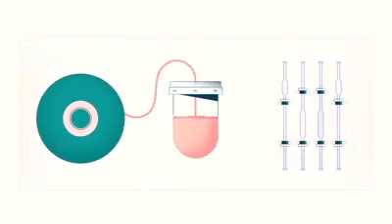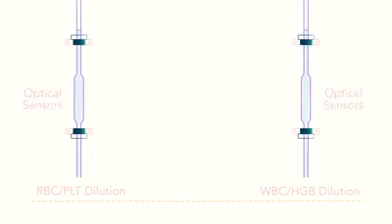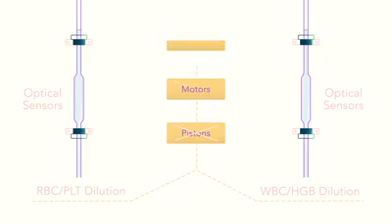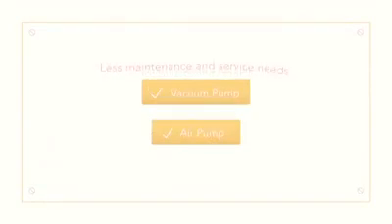This is the first step in the dilution process. From here on, the diluted sample is divided into two different paths. They both go through a second dilution process using pipettes, featuring optical sensors, guaranteeing an accurate volume. No pistons, motors, or gearboxes are used in the diluting system.